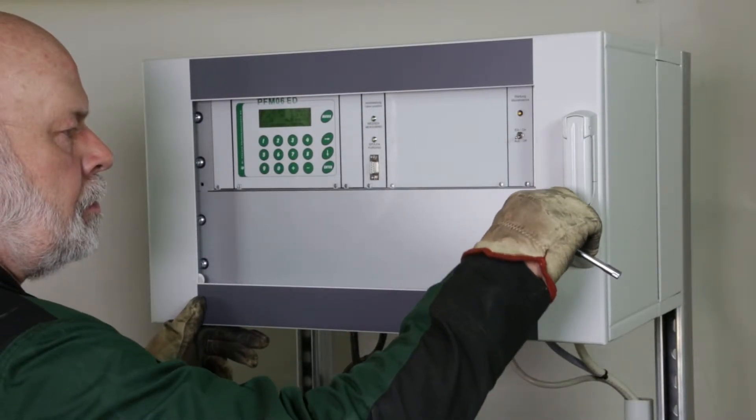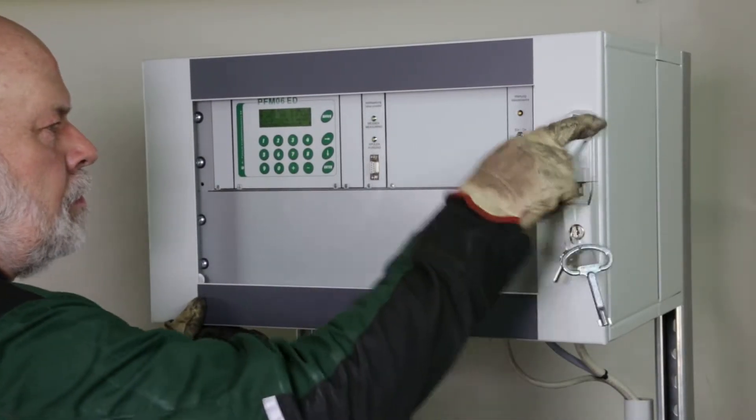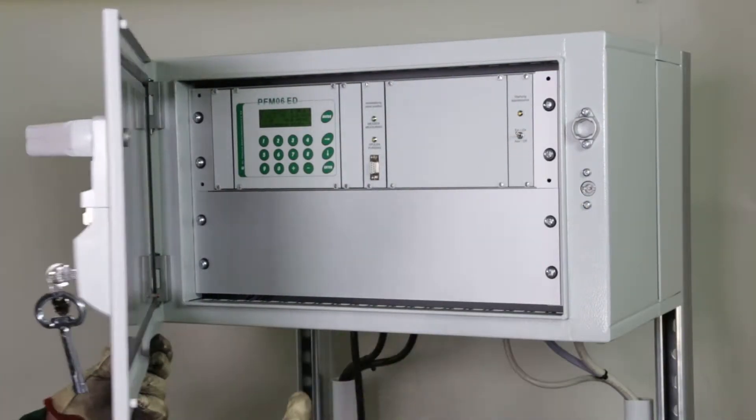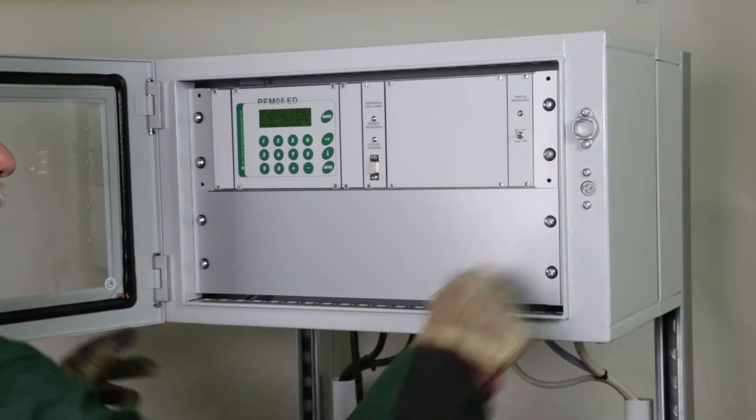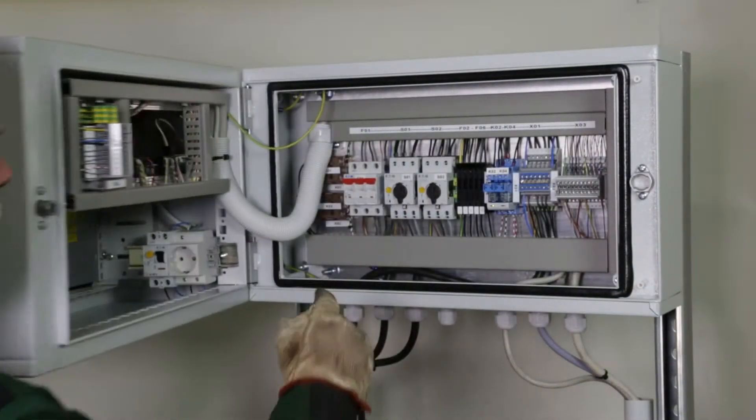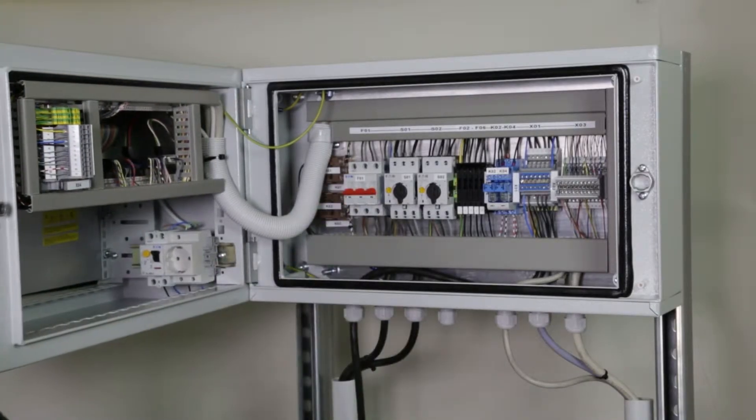Check the values for plausibility monthly. Readjust the flows if necessary. Check and clean or change the filters of the blowers and the sampling probe ventilation regularly. Clean the sampling probe every three to six months.